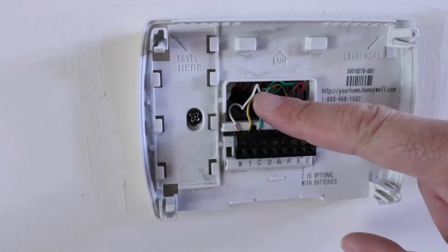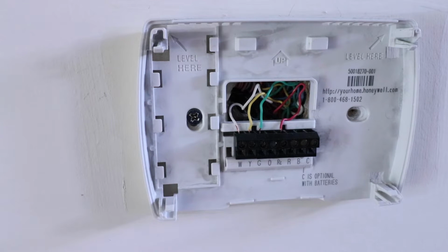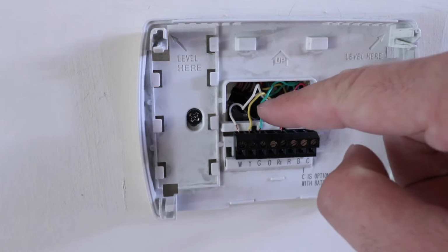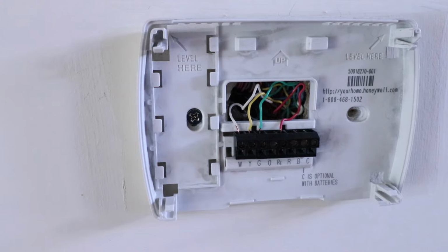So we're going to take that G wire and move it over to the C terminal on the Wyze thermostat, and that's how we'll install this without a common wire. We're going to repurpose that fan wire because we don't need it for our HVAC system to operate properly in most cases.